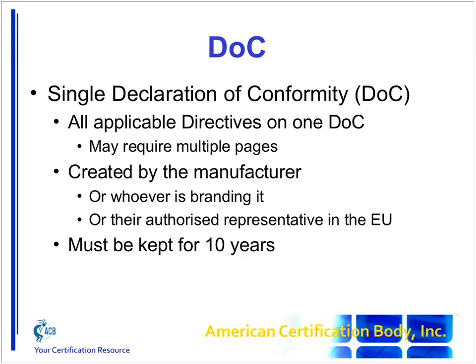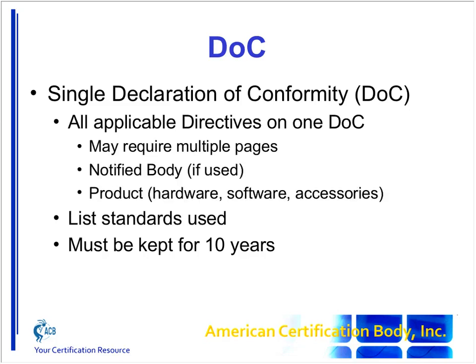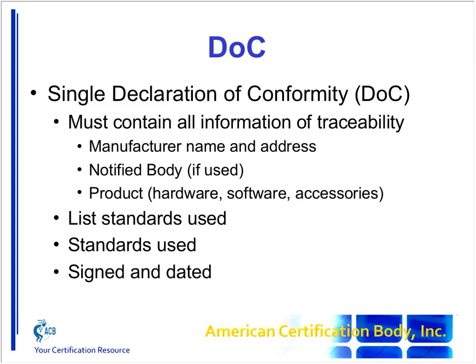The DOC must contain all information for traceability, such as the manufacturer's name and address. It must reference the notified body if you used one, and the product itself, including hardware versions, accessories like antenna types, and software versions if that affects compliance. They're all listed on the DOC, which should always list the standards used and have a signature.